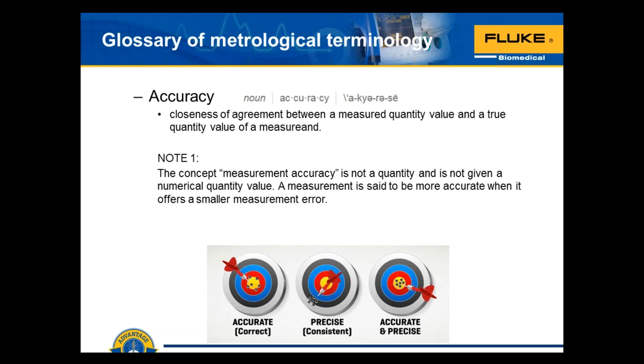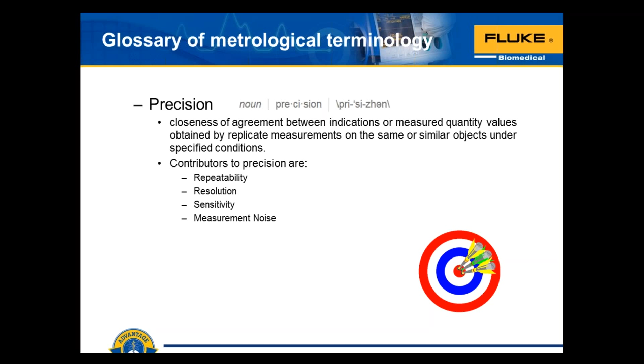You can have a tight pattern but not be in the bullseye at all for a lot of different reasons. What we want as biomedical engineers across the world is both accuracy and precision in the measurements that we're making. Resolution is a different question, and we can talk about resolution on a different day. Precision is the closeness of agreement between indications or measured quantity values that are obtained by replicate measurements, so repeated measurements, on the same or similar objects under specified conditions. So we're just making sure that we control the variables and that we're making the measurement the same way each time. And then we're trying to judge, do we just have a tight pattern here, or is it both precise and accurate, meaning everything's in the bullseye?